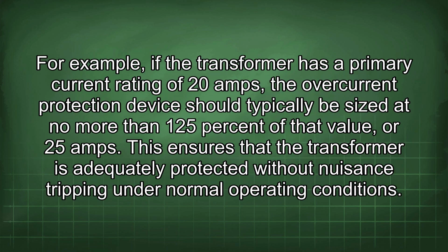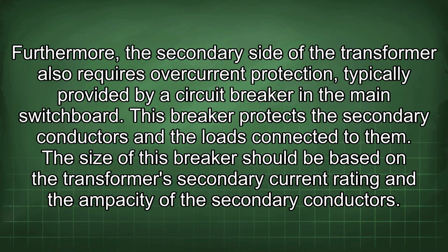For example, if the transformer has a primary current rating of 20 amps, the overcurrent protection device should typically be sized at no more than 125% of that value, or 25 amps. This ensures that the transformer is adequately protected without nuisance tripping under normal operating conditions. Furthermore, the secondary side of the transformer also requires overcurrent protection, typically provided by a circuit breaker in the main switchboard. This breaker protects the secondary conductors and the loads connected to them.